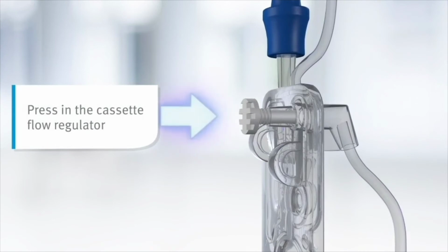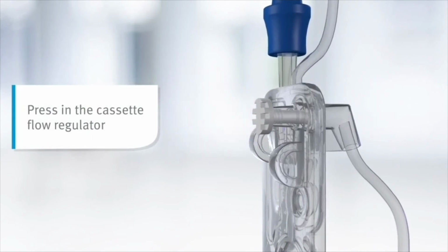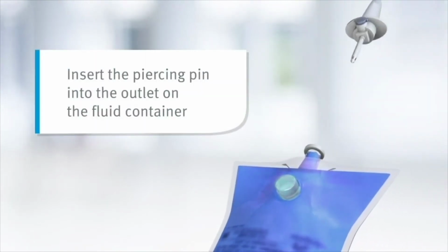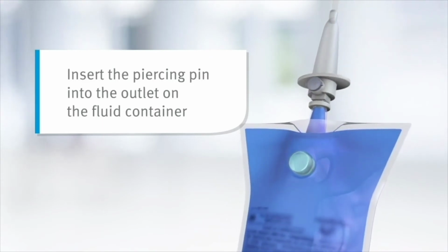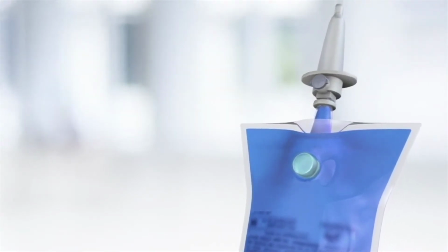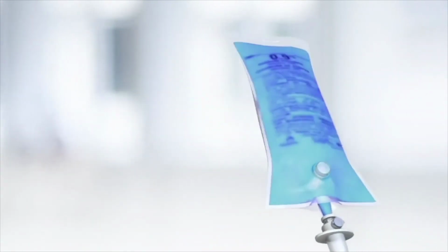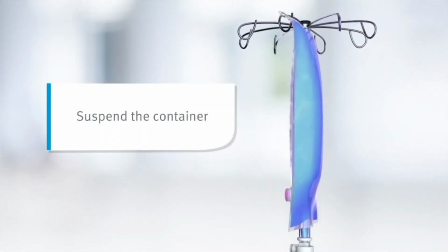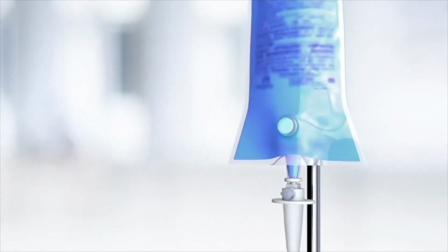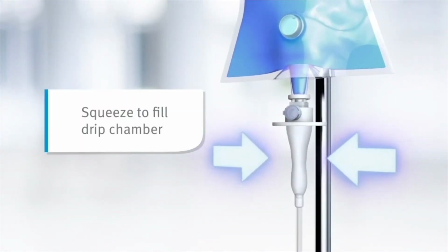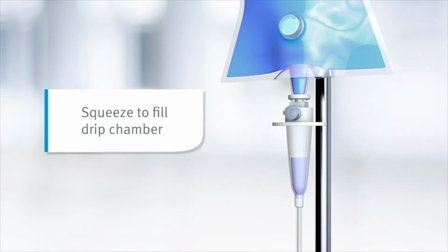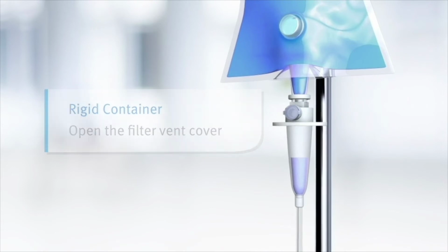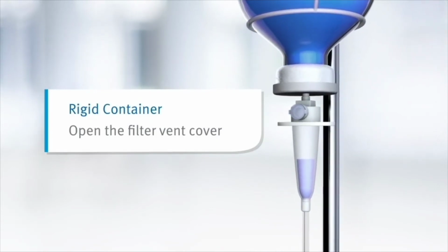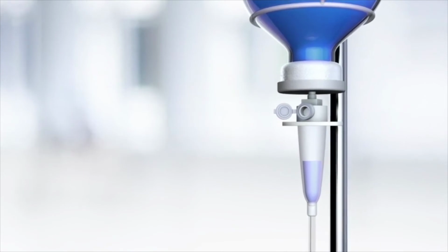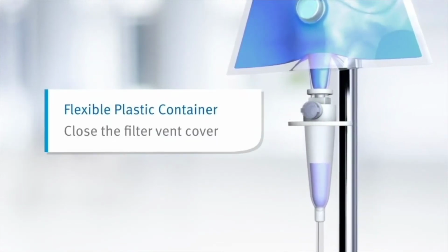Press in the cassette flow regulator to make sure it is closed and confirm that there is no flow during priming. Insert the piercing pin into the outlet on the fluid container using a twisting motion. Do not insert the piercing pin while the container is hanging above the infuser. Suspend the container on the IV pole. Squeeze to fill the drip chamber to the score mark. Do not completely fill the drip chamber. If using a rigid fluid container such as a glass bottle, open the filter vent cover above the drip chamber. If using a flexible plastic container, make sure the vent cover is closed.